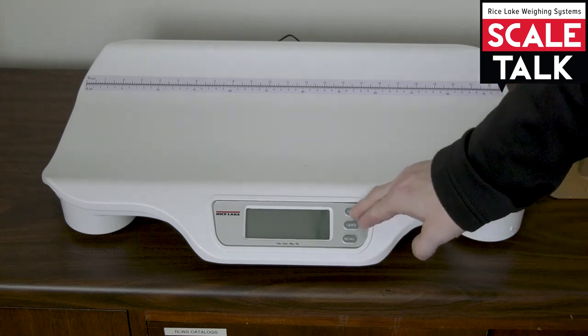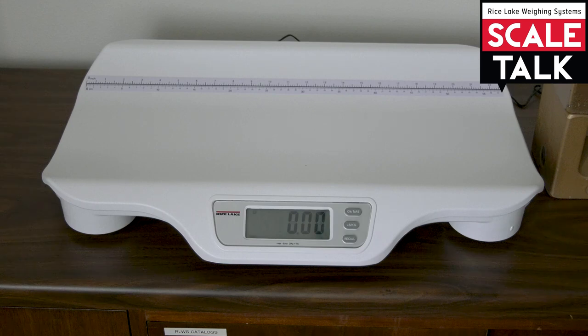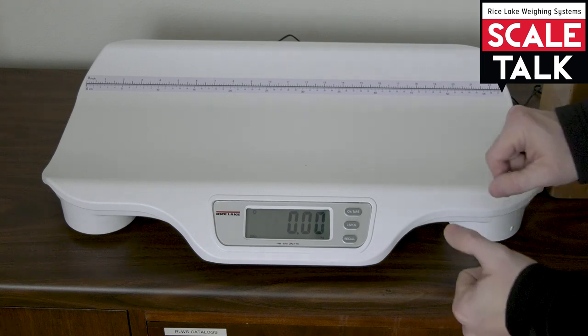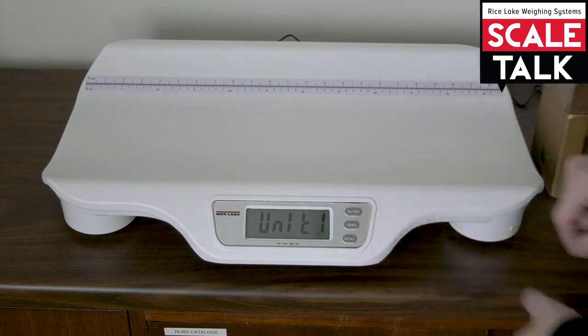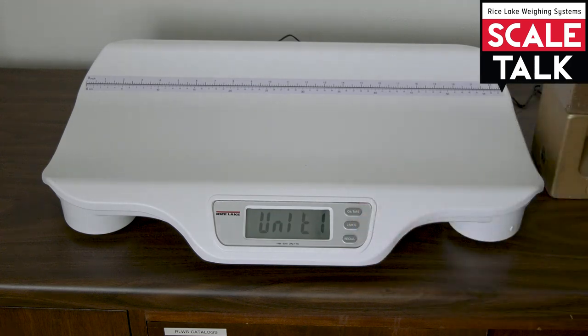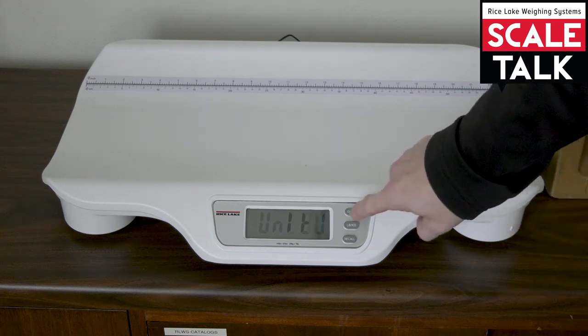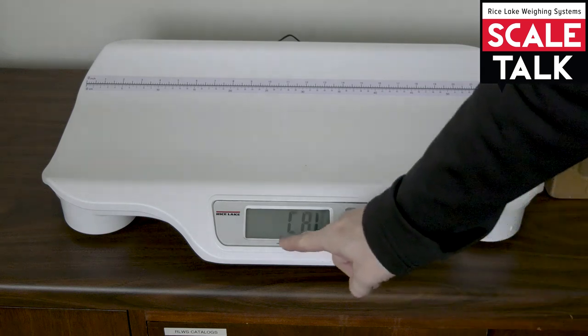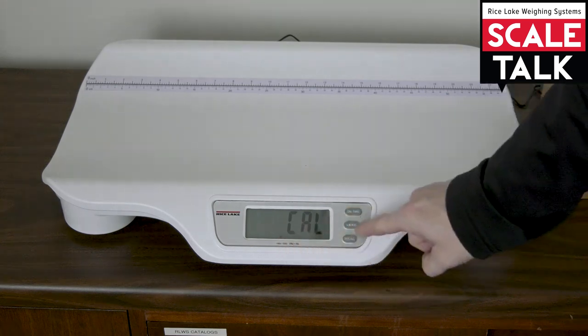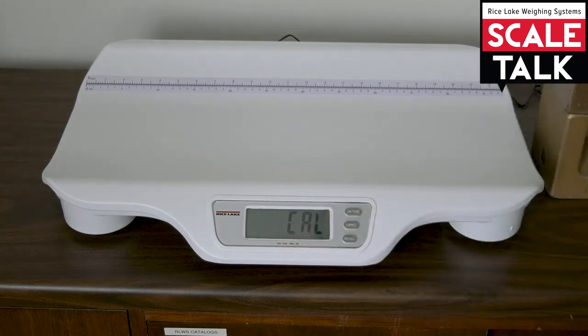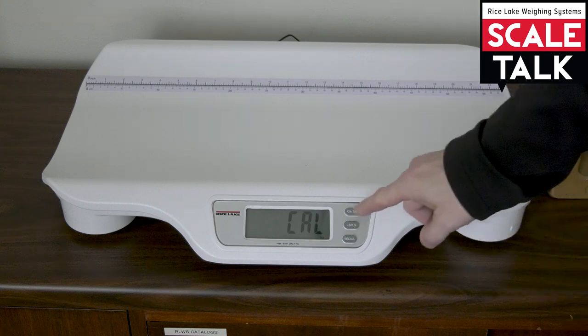So we'll have to start by powering the unit on, and once we get to our operation mode here, we're going to go ahead and press the on-tare keys and the pound kilogram keys at the same time. The display should say Unit 1. Then we'll go ahead and press the on-tare key until it says Cal. And we see that the pounds annunciator here is lit. We're going to hit pound kilogram to change that over to kilograms. And now the unit is set to request metric weights for the calibration.